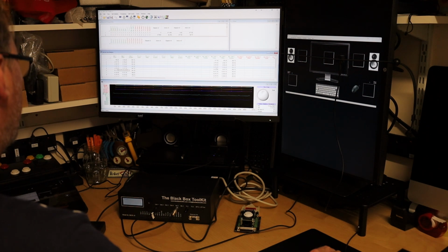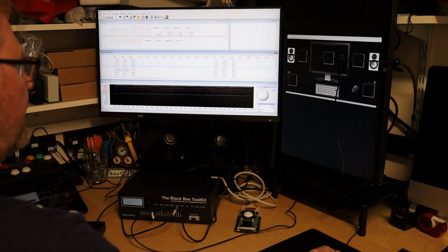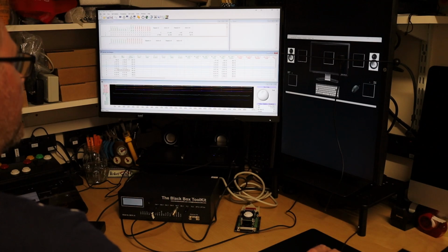So we can see that that's quite a bit different. So it's about 50 odd milliseconds difference. So again, without this equipment, you wouldn't know that you got an error, and you wouldn't know that your event marks were out as well. So basically your digital event marks would be incorrect because you actually triggered them at the wrong time.